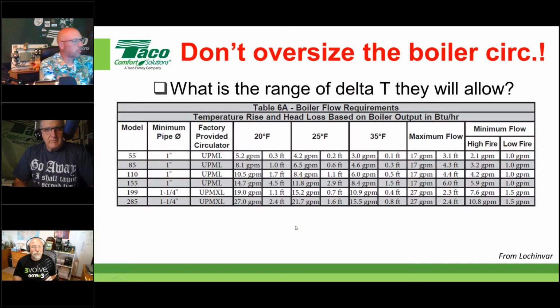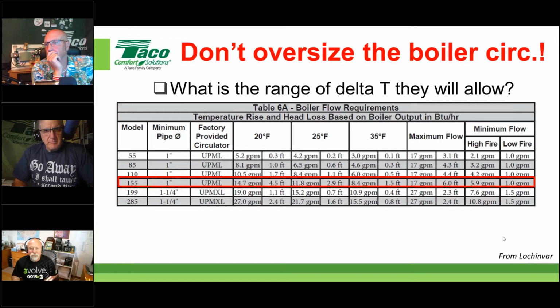Let's go to the boiler manufacturers. For the sake of time tonight, we're just going to show you a couple of them and make this a little bit faster. I'm going to pick a boiler that's around 150,000. This happens to be a 155, from this manufacturer right here. And what I want you to understand is what they allow you to do in writing. In this case, they show you a 20-degree delta T, a 25, and a 35-degree delta T. They also show you the maximum flow they would ever want to see, and the minimum flow at both high and low fire. Just make note of that.